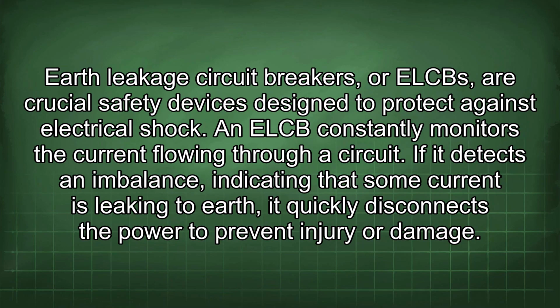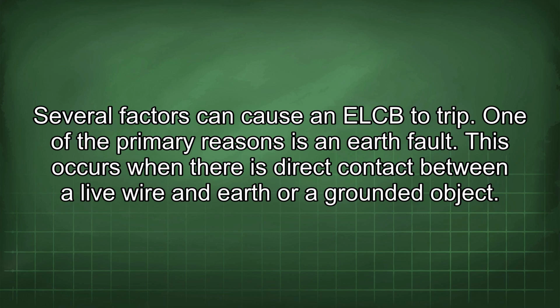Earth leakage circuit breakers, or ELCBs, are crucial safety devices designed to protect against electrical shock. An ELCB constantly monitors the current flowing through a circuit. If it detects an imbalance, indicating that some current is leaking to earth, it quickly disconnects the power to prevent injury or damage. Several factors can cause an ELCB to trip.